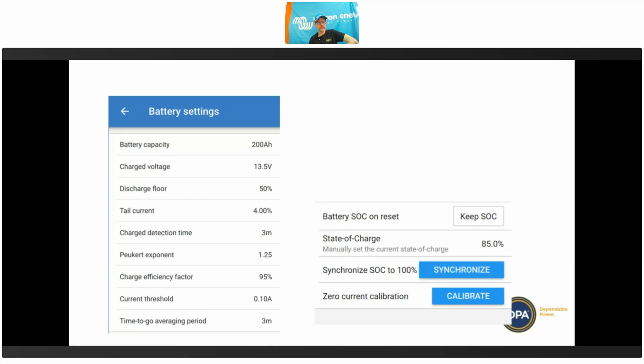You can recalibrate the shunt if you need to. You very rarely will need to do that. If you do need to recalibrate it, if you're looking at the shunt's values and you know there's 10 amps coming out, but it's reading 8 amps, then what you need to do is remove the negative connection on the load side of the shunt so that there's no possibility of any current flow, and then you press the zero current calibration in the app here, and that will calibrate it. You can also synchronize to 100% as well. Again, sometimes you might need to use that feature, but most of the time, you're better off just letting it charge all the way up, and then it will calibrate itself.